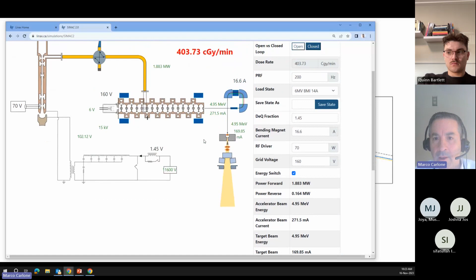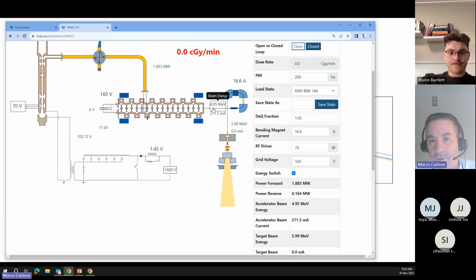And I can easily show that just by going back to here and typing in the original bending magnet current that we had, and rerunning that. So if I run that again, now the bending magnet current wants to let a different energy beam go through. It wants to let 6 MeV electrons go through. None of them get through because the accelerator is making 4.95, and the dose rate goes to 0.